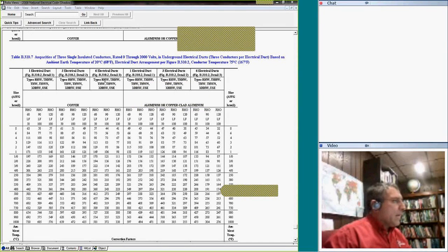The table I use, duct 6 electrical ducts. Can you guys see that detail number 3? The one I just showed you. 6 electrical ducts. Since it's underground, I'm going to be using XHHW, and I have a 500 kcmil conductor. With that 500 kcmil conductor, if you put 3 of them in a duct bank like this, you can see the amps. With this you can carry 412, 273, and 340.